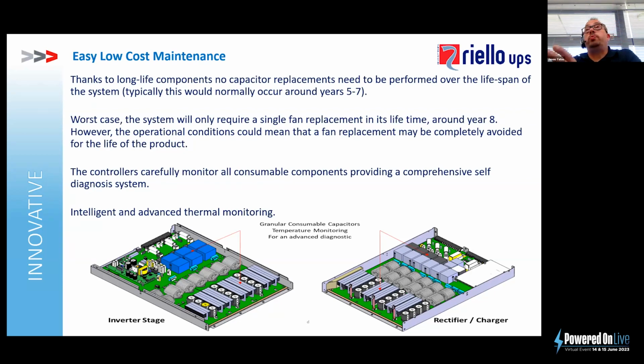Now, typically, a UPS system in operation would require capacitors, fans, etc. changed, typically anywhere between 5 to 7 years. And obviously that's got a significant cost. It's got a reduction in resilience and so on whilst that work is being performed. In this system, we operate long life components, so there is no need to change the capacitors for the full lifespan of the product. In terms of maintenance, the worst case is that the system will only require a single fan replacement in its lifetime. Now, when I say a single fan, I don't mean a single one fan. I mean all of the fans changed once.